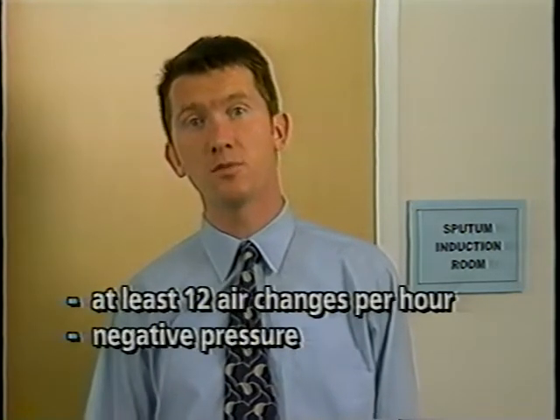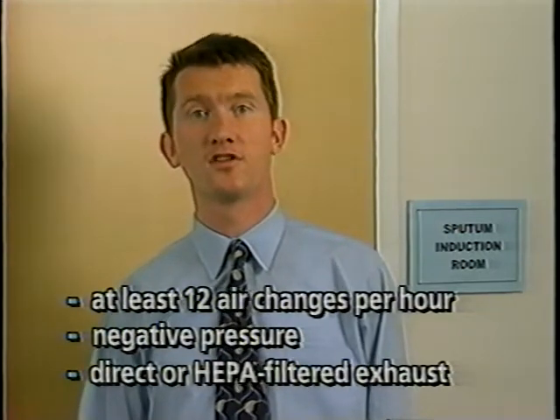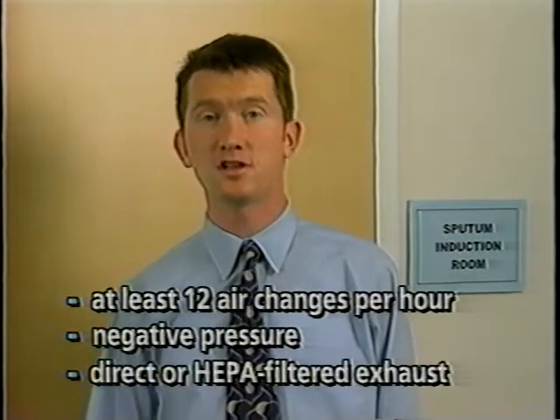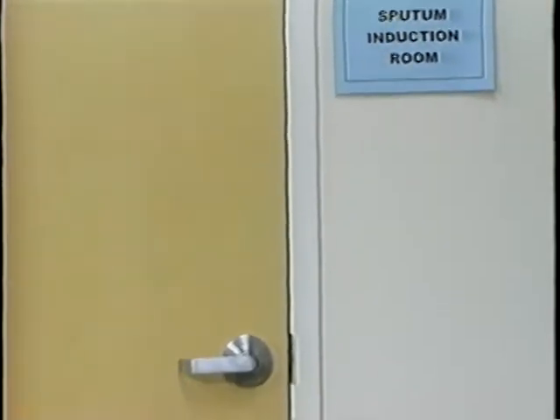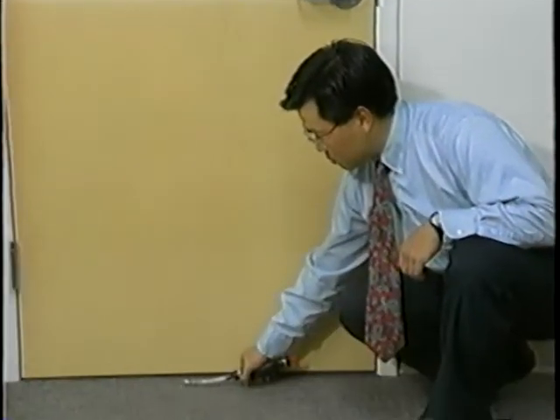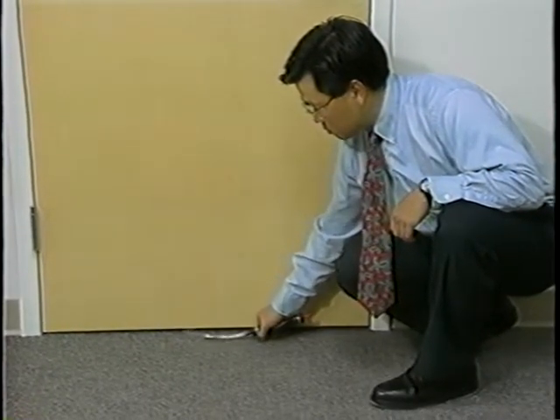If a booth is unavailable, a designated room should be used for sputum induction. Engineering controls should meet all the minimum requirements that we outlined for isolation rooms. That is, at least 12 ACH, negative pressure, and direct HEPA-filtered exhaust. And just like with an isolation room, you'll need to estimate and enforce a clearance time between patients. We also recommend that you verify negative pressure before starting that day's sputum inductions.